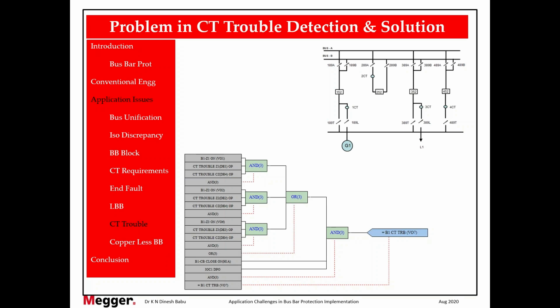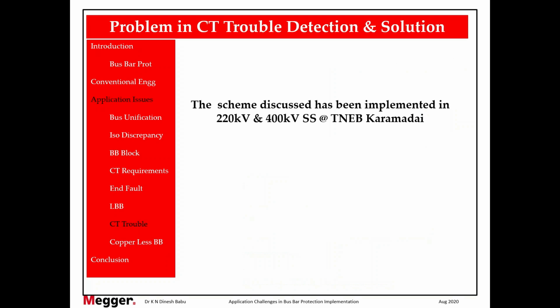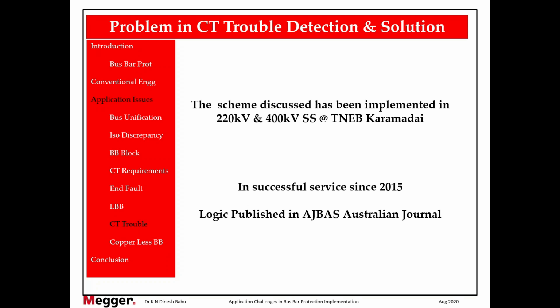So what we see here is not just a theoretical solution. This has been implemented in 400 and 220 kV Karamadai SS of TNEB, and is in successful service since 2015. Moreover, the logic has been published in an Australian-based journal.